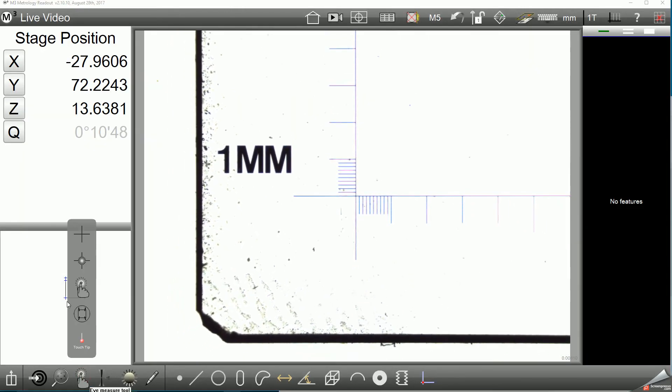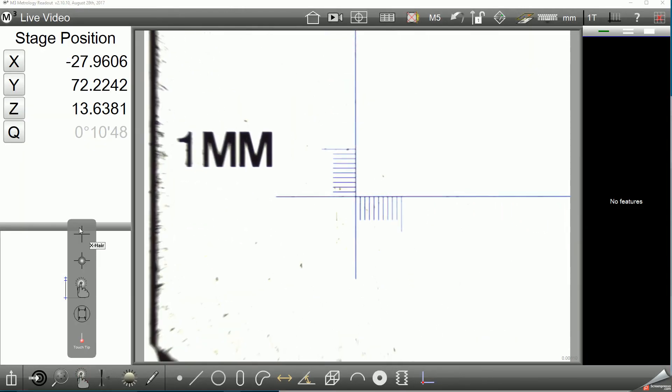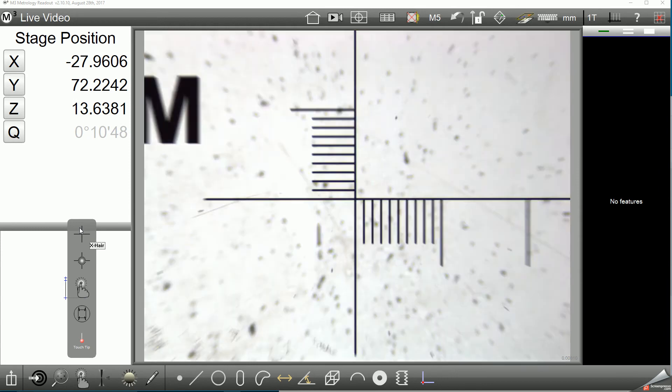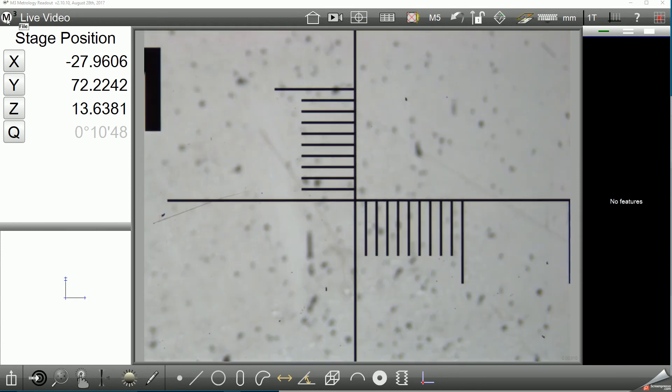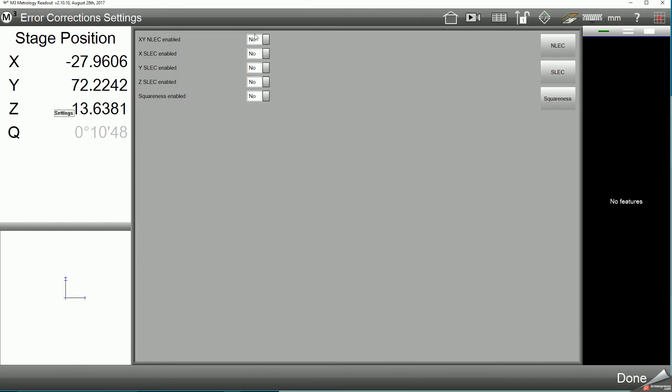Once the system has completed its successful homing, the first thing we should do is enter the M3 setup screen and verify that all error corrections are disabled in the system before proceeding.